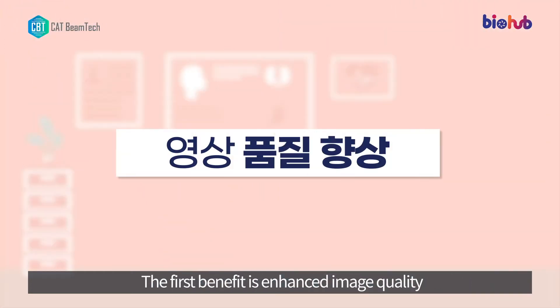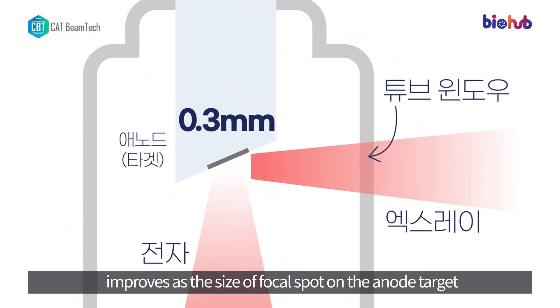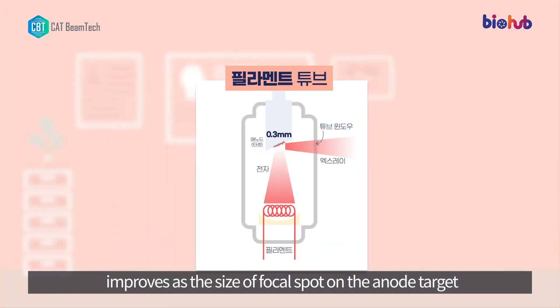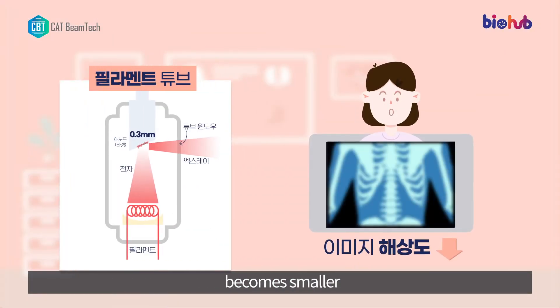The first benefit is enhanced image quality. The resolution of an X-ray image improves as the size of the focal spot on the anode target where the electrons collide becomes smaller.